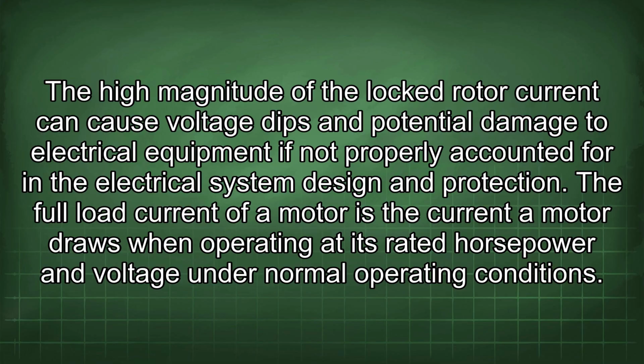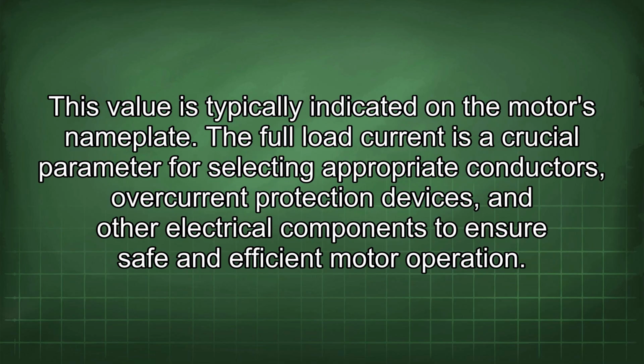The full load current of a motor is the current a motor draws when operating at its rated horsepower and voltage under normal operating conditions. This value is typically indicated on the motor's nameplate. The full load current is a crucial parameter for selecting appropriate conductors, overcurrent protection devices, and other electrical components to ensure safe and efficient motor operation.